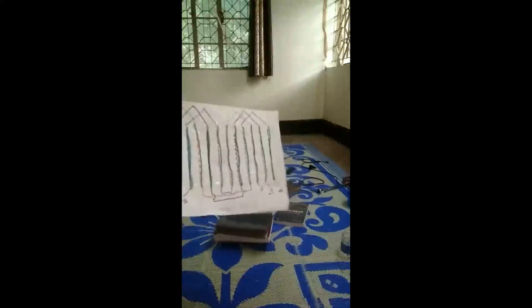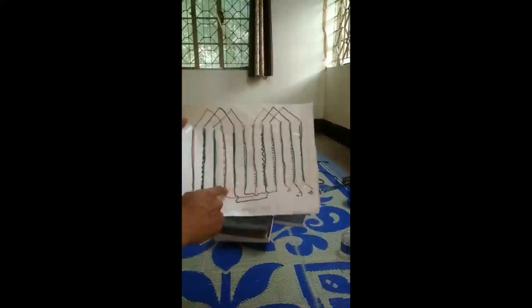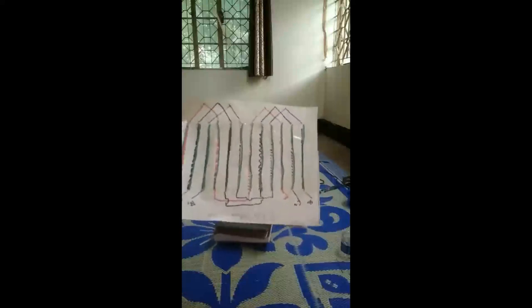You have to short dissimilar ends of the conductors that are 180 degrees apart. Like you have to short A1 with the dissimilar ends of A4, and then the same thing should be repeated for your A7 and A10. Dissimilar ends of A7 and A10 should be shorted, and then the similar ends of these two parallel combinations should be shorted because they are in polarity. So if it was four when you connect all of them in series, after connecting in this parallel form, it will be one.